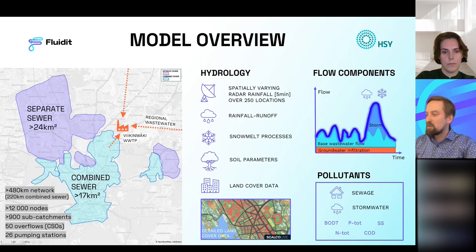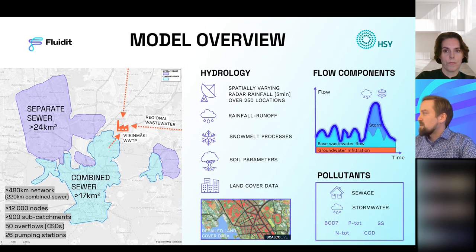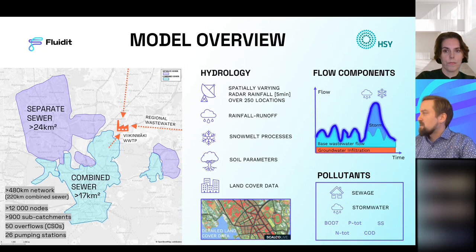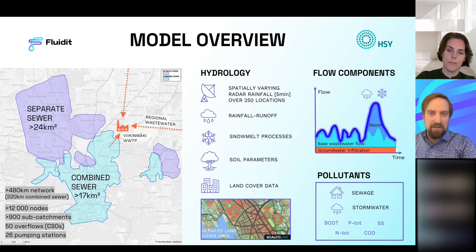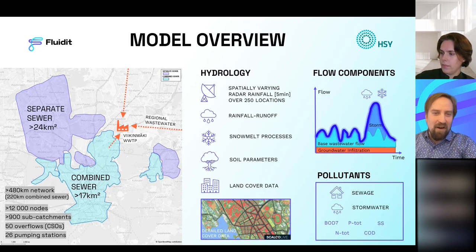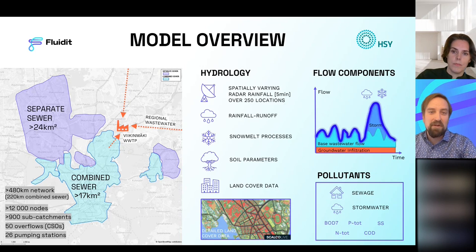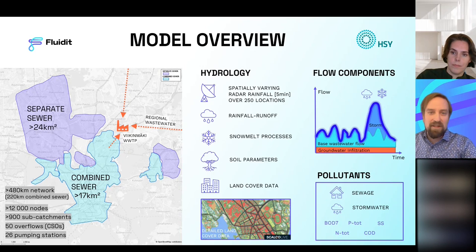The land cover data is a very nice and good dataset in Helsinki — you can separate impervious areas, roads, and different kinds of vegetated areas, and from those you can derive the catchment parameters quite well. The sewer system components obviously include the typical elements like groundwater infiltration and base wastewater flows, which vary based on user patterns. On top of that, we get the interesting part: storm runoff or snowmelt, which cause the highest peaks in the system. Snowmelt can make flows into the treatment plant three times larger than normal during springtime.